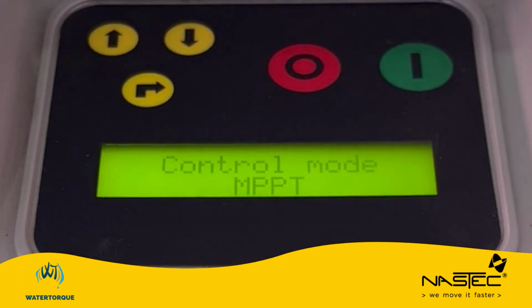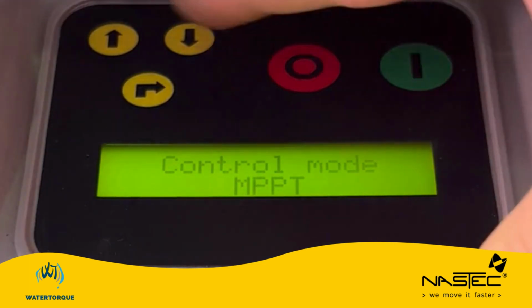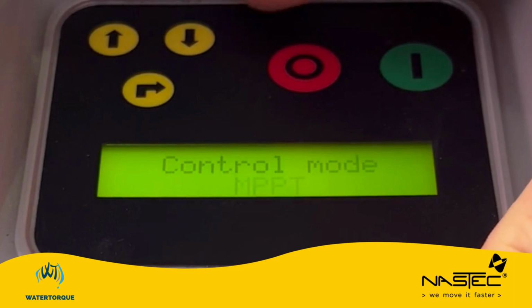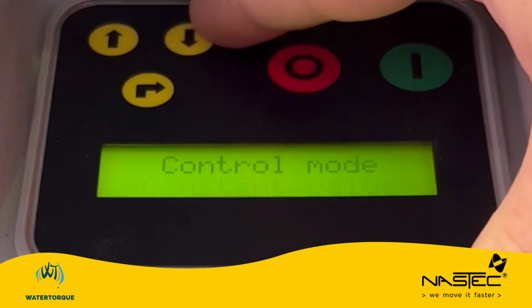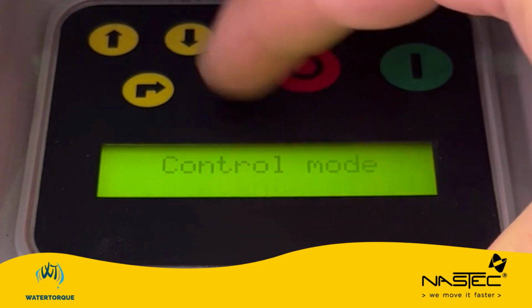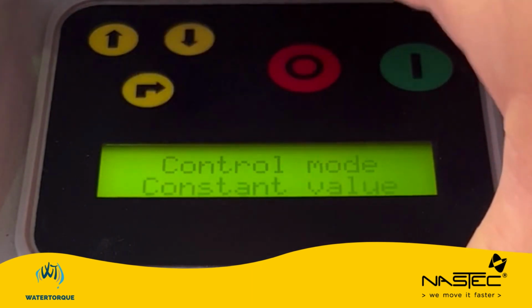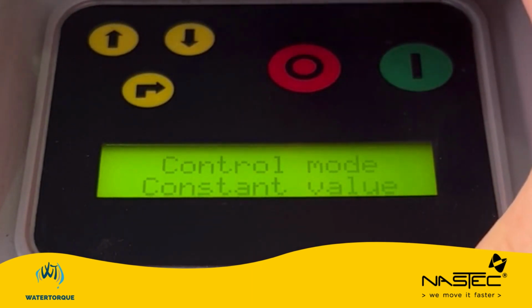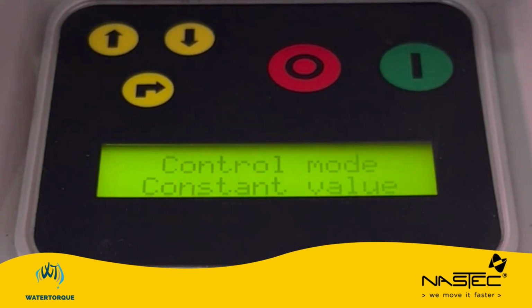Now that takes us into the settings for this particular pump. As I said, we wanted to set this as a constant value mode. So in control mode, we hit the enter button, and we will notice that it's now flashing, and then we hit the down arrow to constant value. Once we see constant value, we hit the enter button. Now that's locked it in.